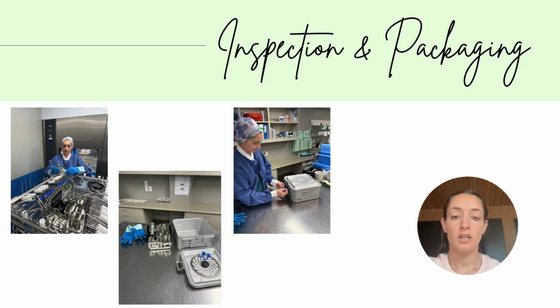For the reamer, I first check the printout when the washer is finished to make sure that the cycle passed and it was on the instrument cycle and not on continuous cycles. Then I write on the washer log document what was in the washer. Then I use some heat protection gloves to remove the whole reamer from the washer rack, and then I put it on the table for inspection.